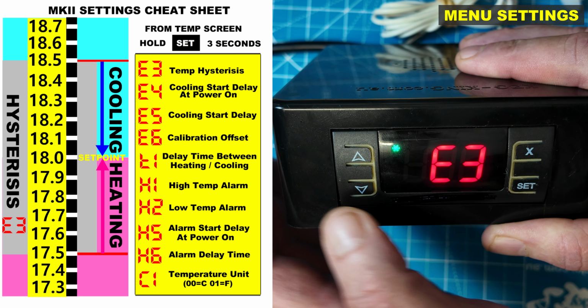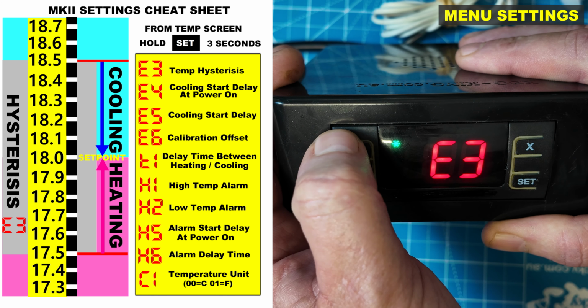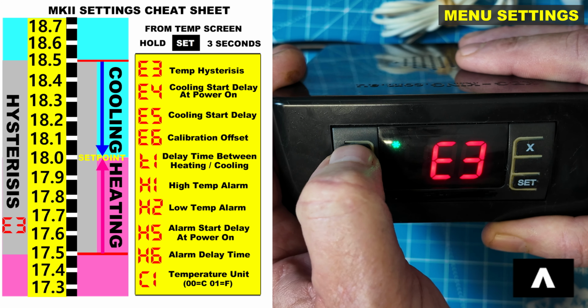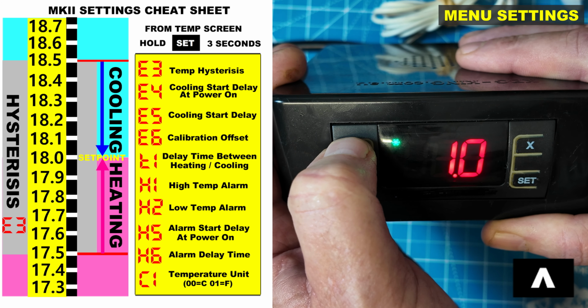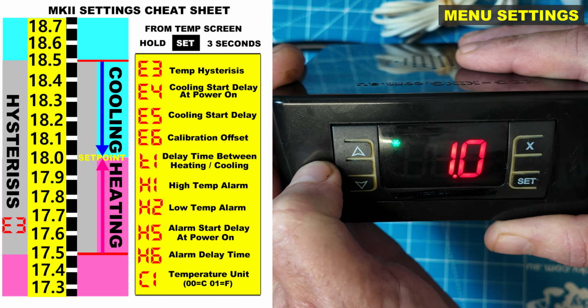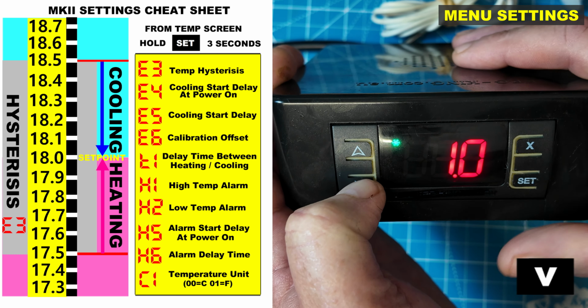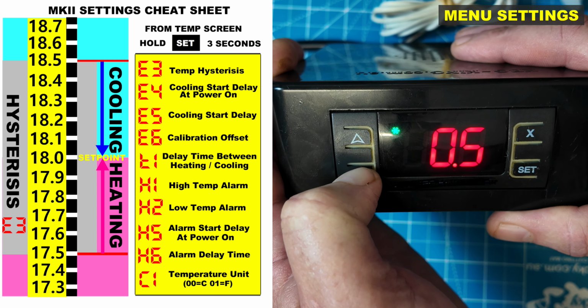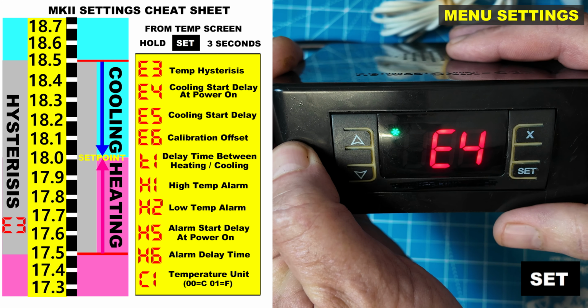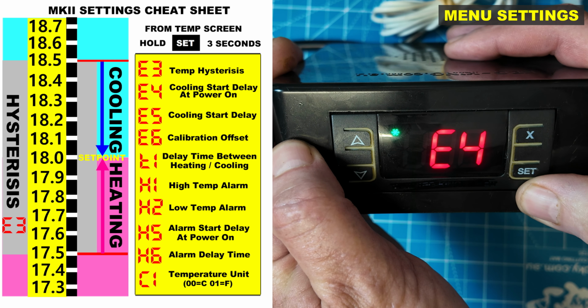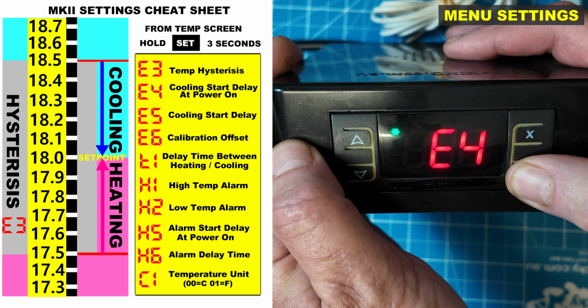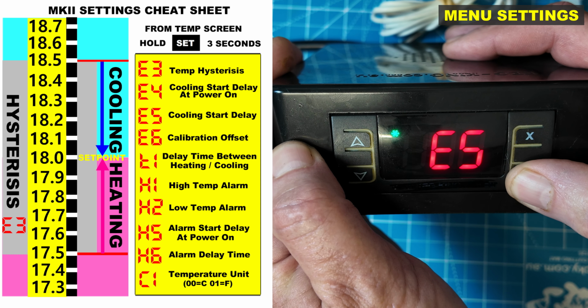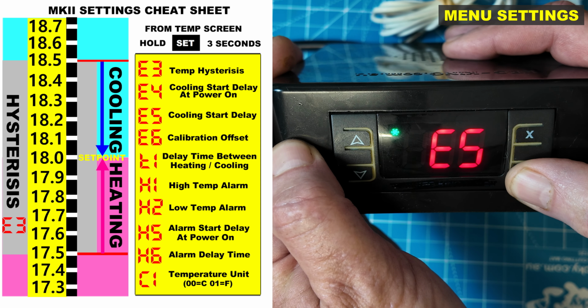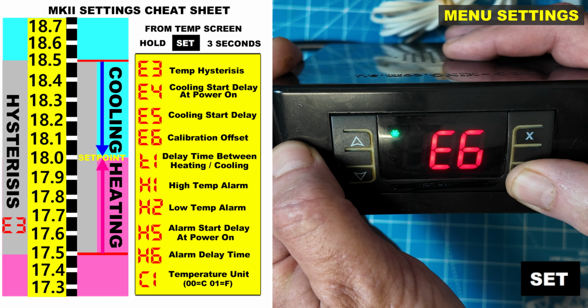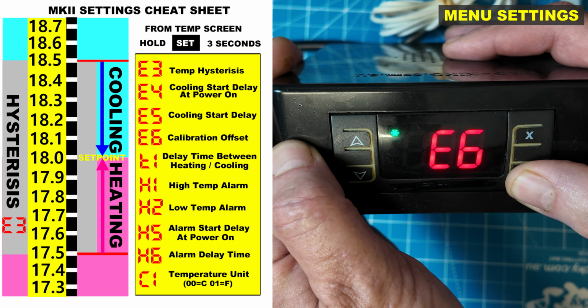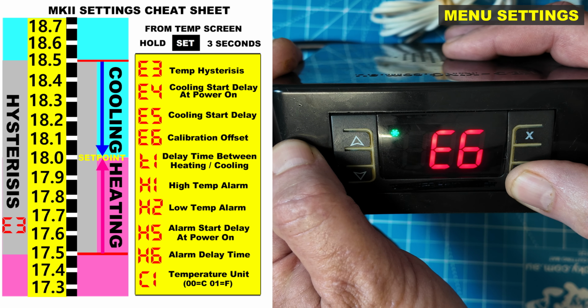First one is hysteresis. That's the temperature buffer before the heating changes. If we go up, we can see that that's set at 1. If we want to change that, again, we can dial that in to 0.5, hit the set button, and we're back at E4. To continue cycling through the menu, we just continue to hit the set button. E5, that is the cooling start delay, an additional delay between cooling cycles. E6 is your calibration offset. It adjusts for inaccuracies in your temperature probe.